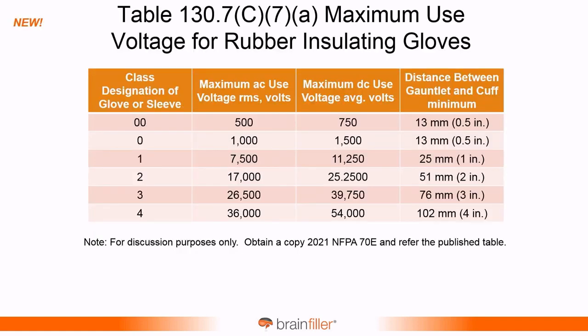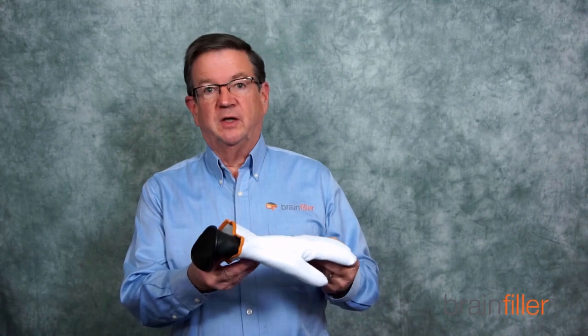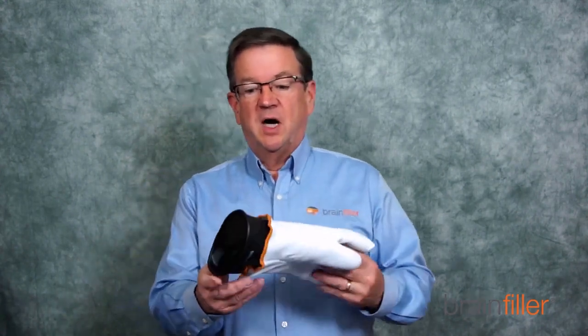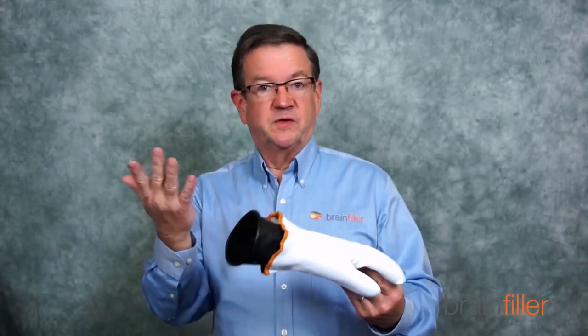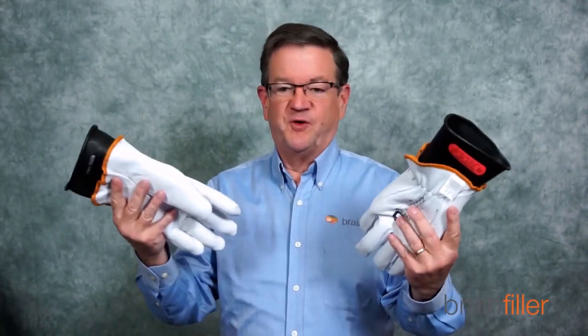And what that table looks like, and notice my note down at the bottom, this is just for discussion. You actually need to use the actual table from NFPA 70E when that comes out. But this shows the different classes of gloves and then the voltage ratings. And on the right, the minimum distance between the gauntlet and the cuff. So that would be like when you have your voltage rated glove and you have your leather protector, the distance from the gauntlet and the cuff. Right in here, there's a certain minimum distance that's required. Usually you far exceed it, but there is a certain minimum distance for that.